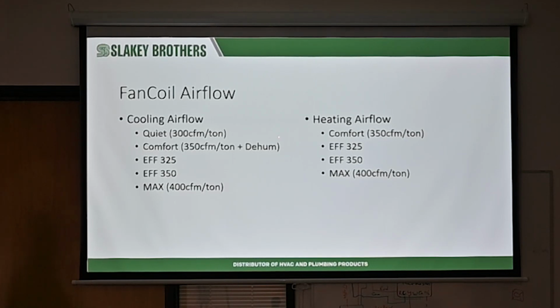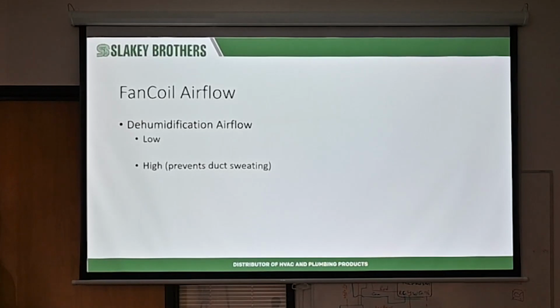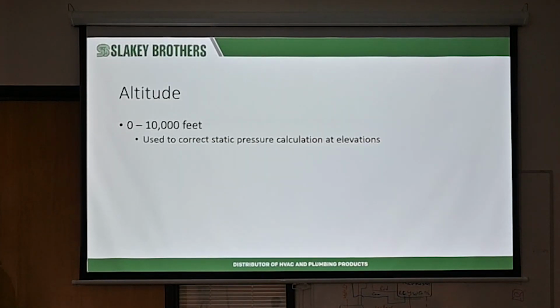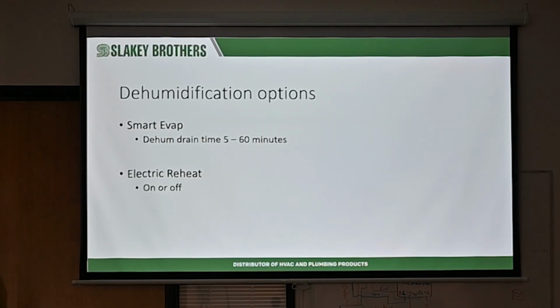If you do this, anytime you do a setup, obviously check your charge, check your temperature split, make sure that too little airflow isn't going to create a problem for that compressor later on. Okay? You've got, again, your dehumidification set points if you're using it. Honestly, I don't remember ever seeing this in the units, but this is just to help calibrate static pressure. I think they're going to default to just fine for where you guys are at here for our elevation. Even where I'm at, it's fine where it's at.